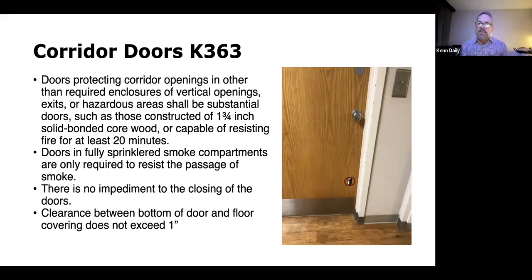In fact, one of the ways I verified this is that I was in a storage room, and the back of the storage room door was gone. Somebody beat it in, left a hole, and I could see that it's hollow to the other side. So hollow doors are not permitted on corridor doors. They have to resist the passage of smoke for no less than 20 minutes. And so that ends up being the gap on the door.